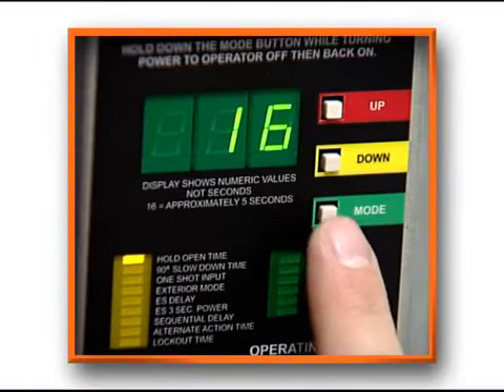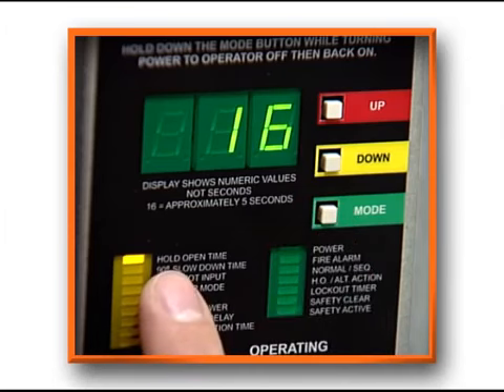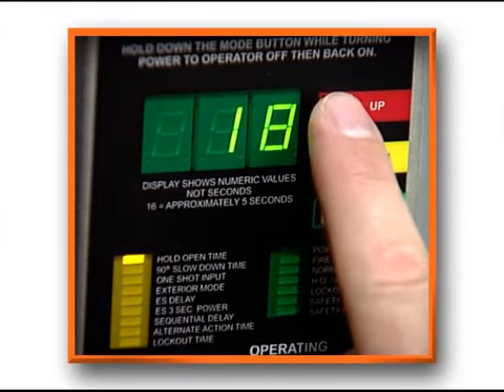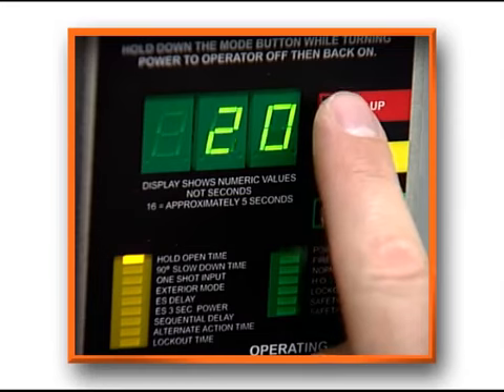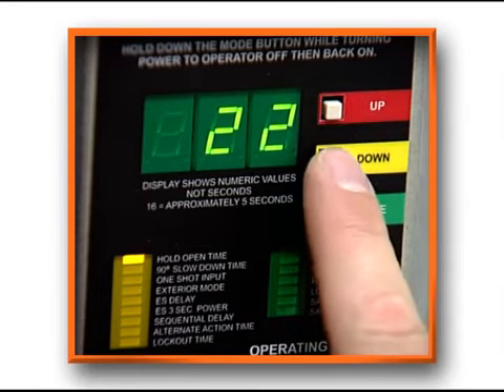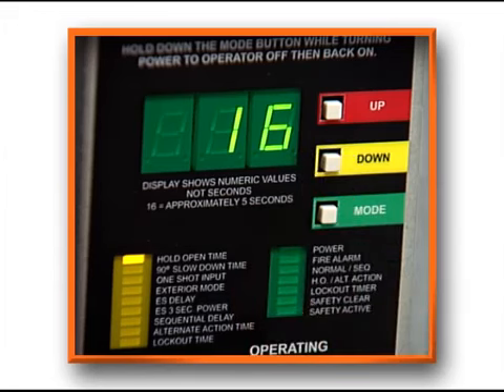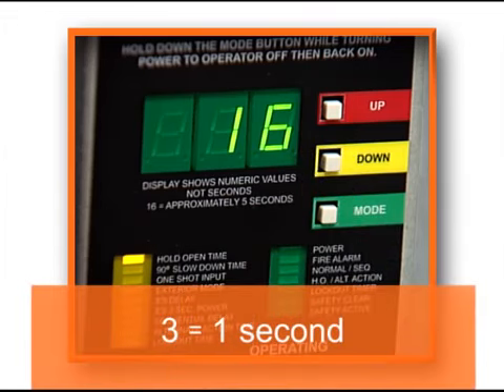The first mode you can adjust is Hold Open Time. This is the length of time the door remains open after reaching the 90-degree position. To change this setting, press the up or down button. Setting options run from 0 to 999, and the default setting is 16, or approximately 5 seconds.